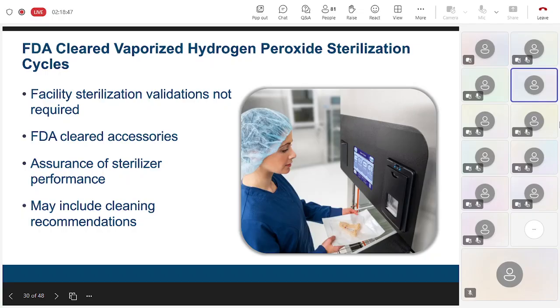Since the cycle is validated and FDA cleared and issued with 510K certification, 3D printed guides and models that meet its specifications would not require sterilisation validations, and that would save the healthcare facility time and money. The sterilizer cycle would have FDA cleared accessories for the cycle and 3D printed guides and models, so you wouldn't have to revalidate your accessories. The manufacturer would also have an appropriate preventative maintenance plan and confirm sterilizer performance of the cycle. In some cases, the cleaning recommendations may also be available, which would eliminate the need for cleaning validations.